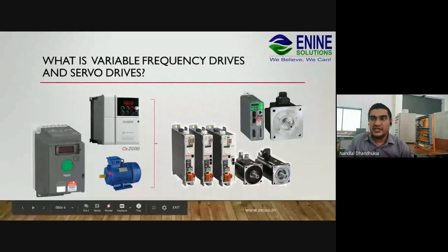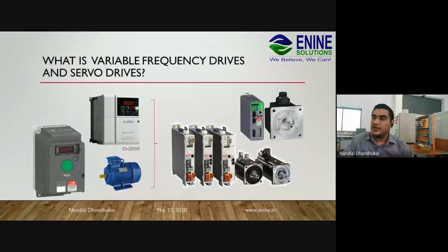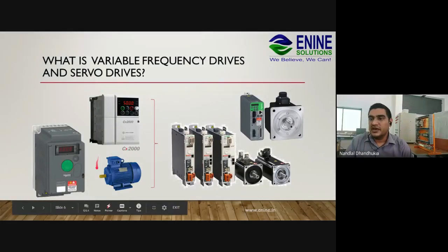Now, where are AC drives used and where are normal motors used? Suppose you don't need any precise length cutting mechanism, you just want to control the speed of a fan, or control the speed of a pump for supplying water, or just want to save electricity using a variable frequency drive. In those applications, you can use an AC drive with a motor.